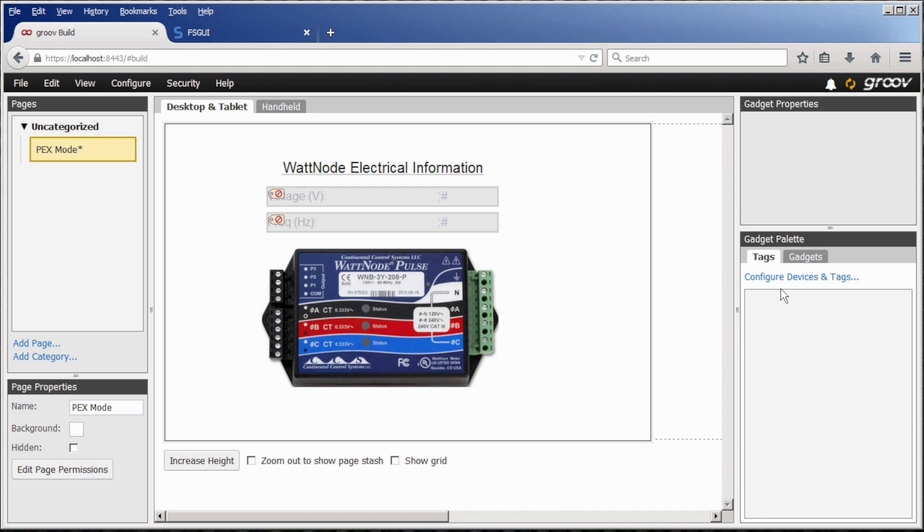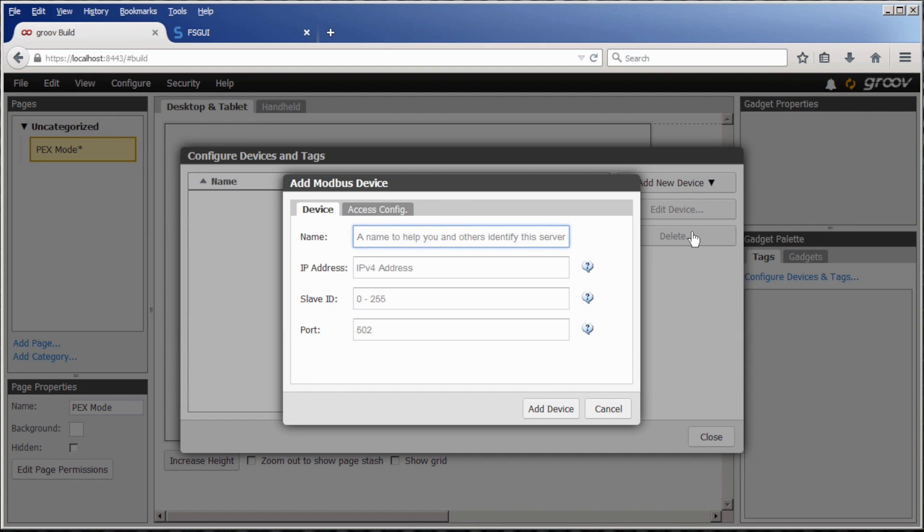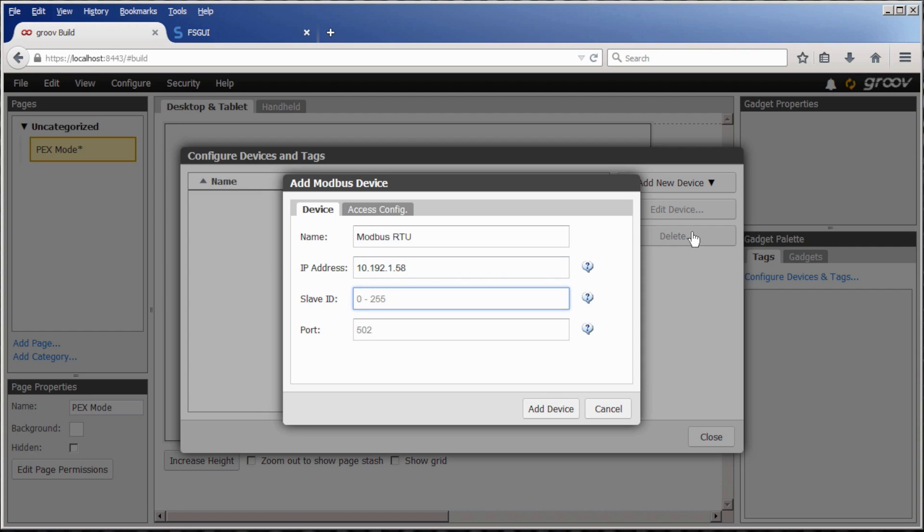To add the Modbus device, we are actually adding the quick server gateway. Go to configure devices and tags, and add new device. Select Modbus device, give it a name like Modbus RTU, then put in the IP address of the quick server. In our case, it's 10.192.1.58. Next, define the slave ID, which is set on your Modbus RTU device. My device is set to 4.